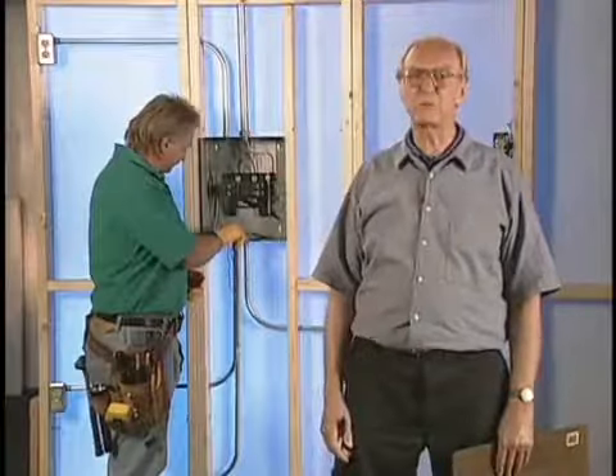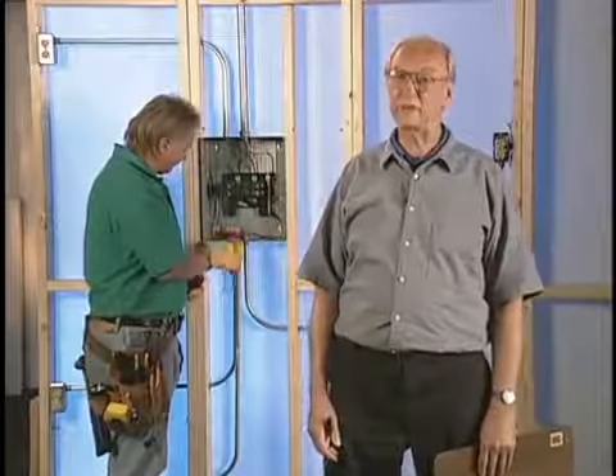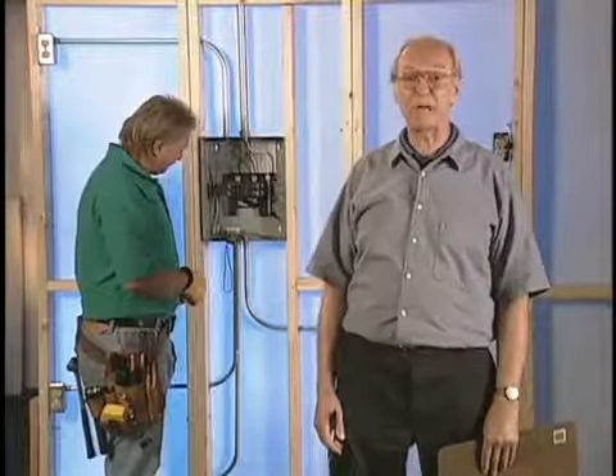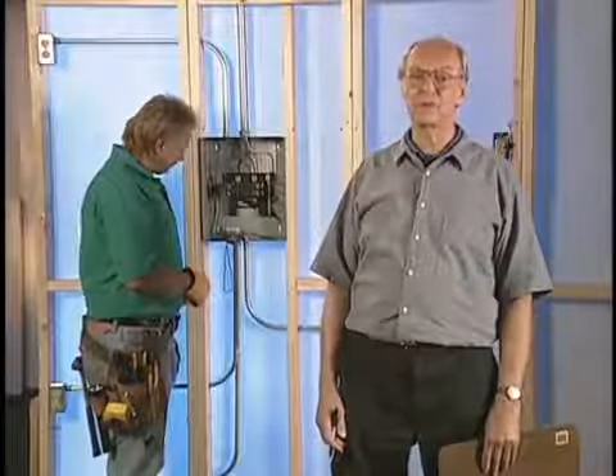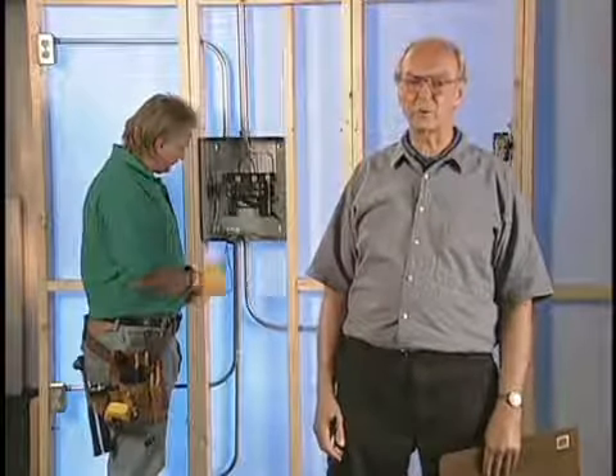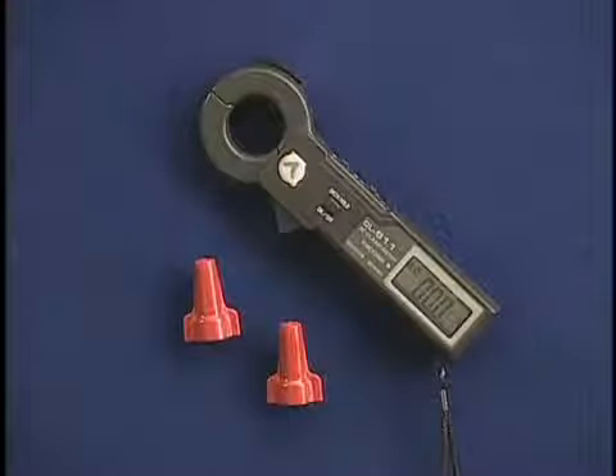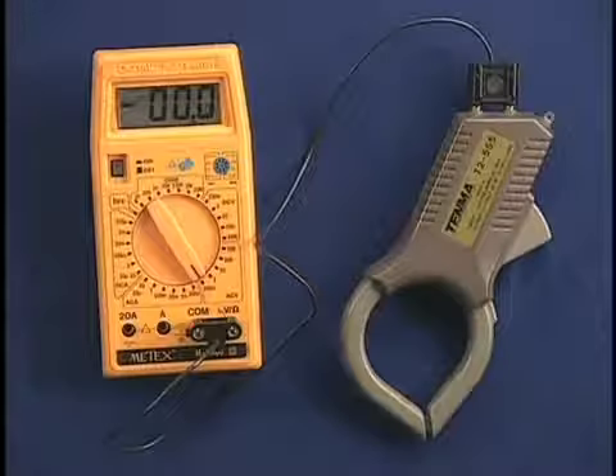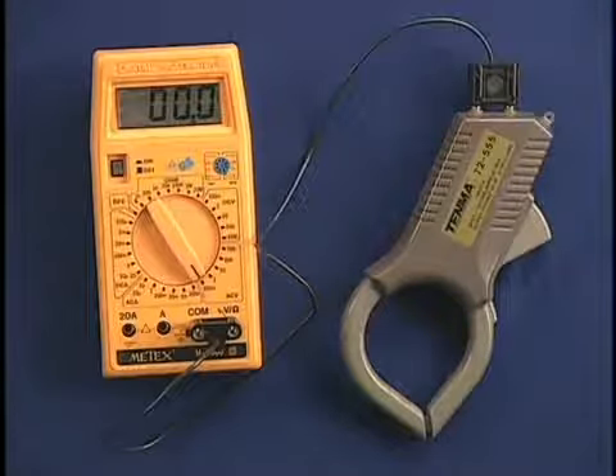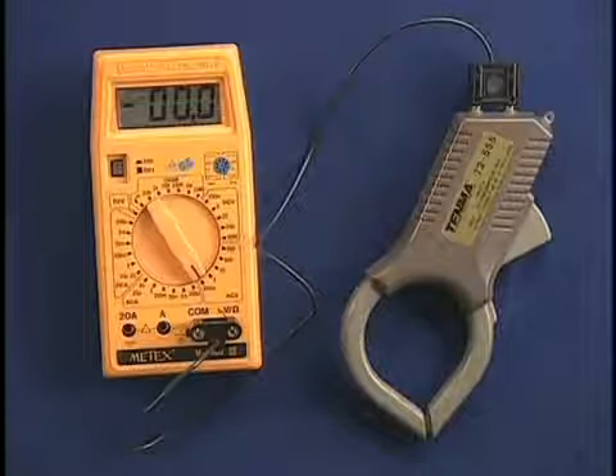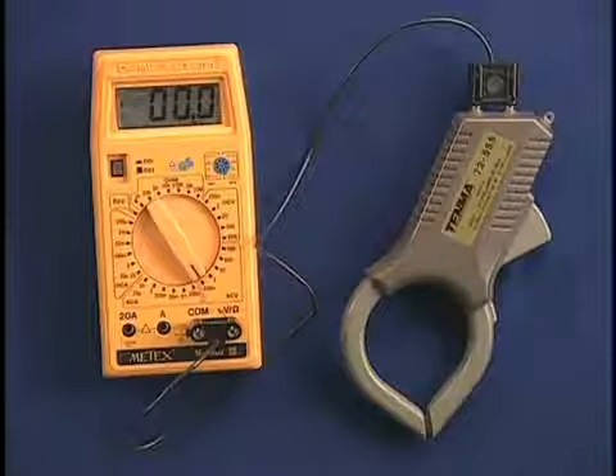But to perform a simple procedure such as this may be impossible if your clamp-on ammeter is the wrong size. So let's take a moment to check our tools. This mini clamp-on is very easy to use and will get around small groups of conductors as well as around small conduits. See your handout for details on all these meters. Also very useful is this inexpensive probe with thin jaws for larger conductors and conduits, and some water pipes.